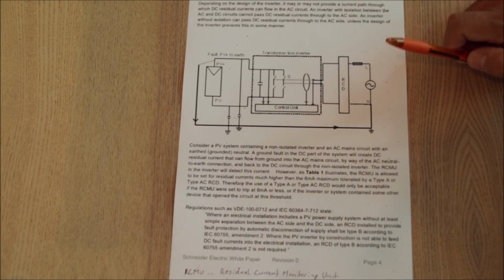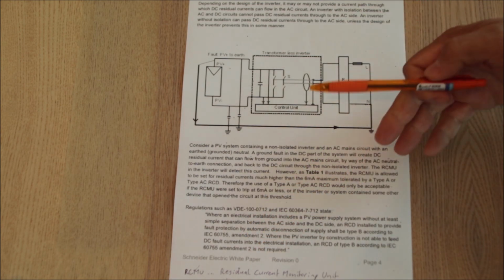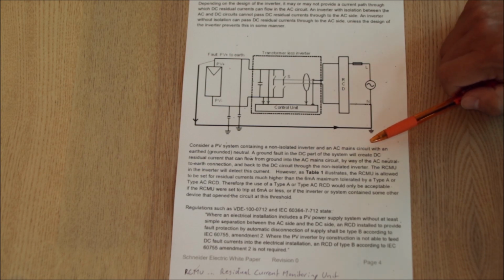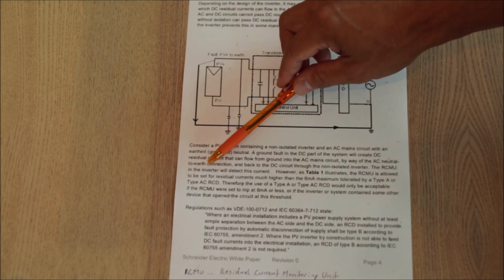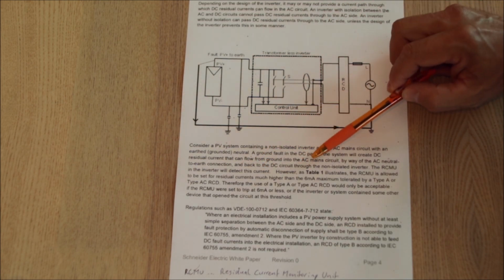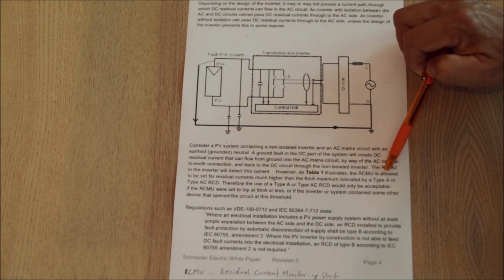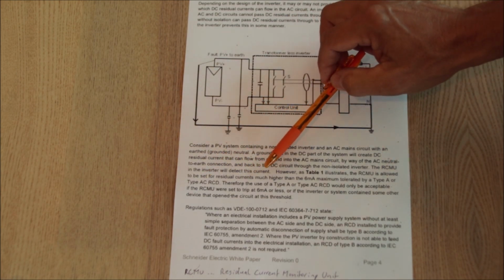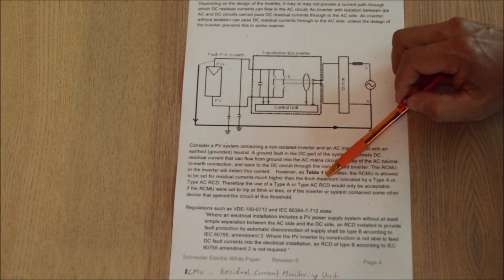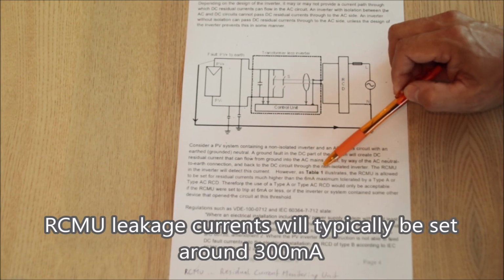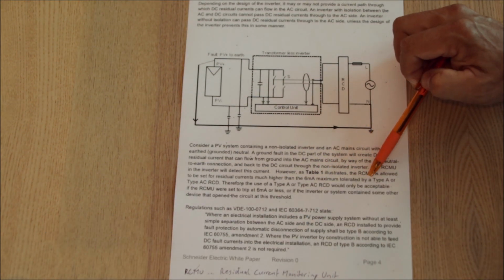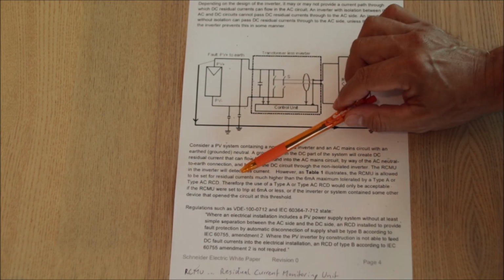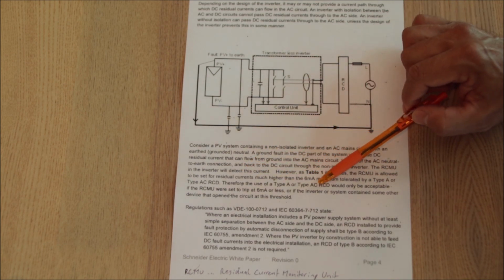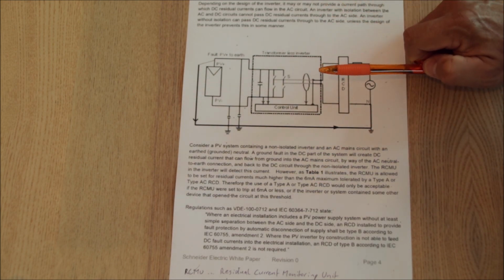RCMU stands for Residual Current Monitoring Unit. So there is an electronic circuit inside the inverter which is trying to identify those sort of leakages also, right? The RCMU in the inverter will detect this current. However, the RCMU is allowed to be set for residual currents much higher than the 6 milliamp. 6 milliamps is usually what the RCDs are set as maximum tolerated value. Therefore, a Type A or Type AC RCD would not be acceptable, right?